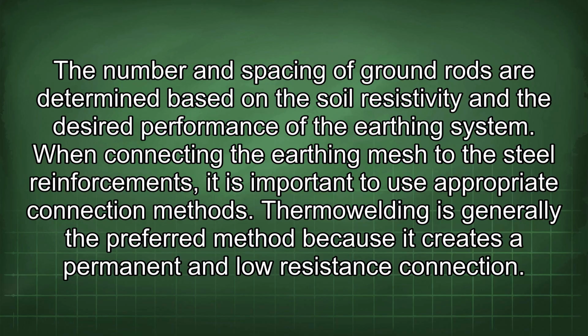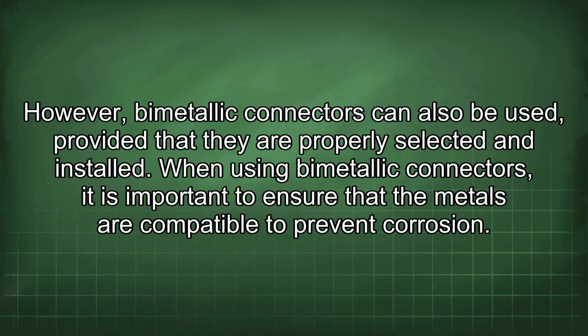When connecting the earthing mesh to the steel reinforcements, it is important to use appropriate connection methods. Thermowelding is generally the preferred method because it creates a permanent and low resistance connection. However, bimetallic connectors can also be used, provided that they are properly selected and installed.